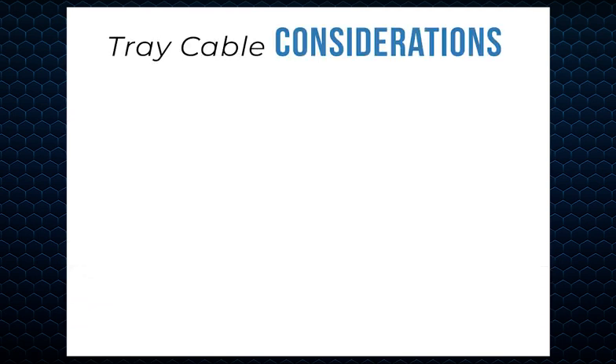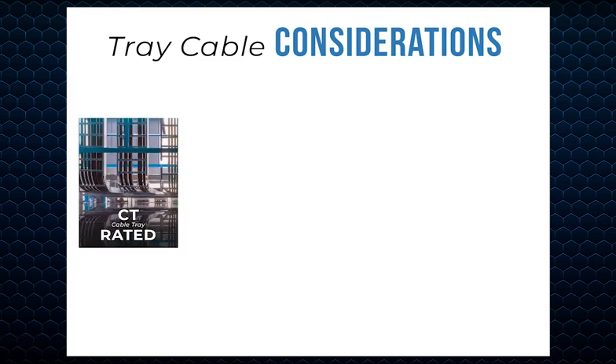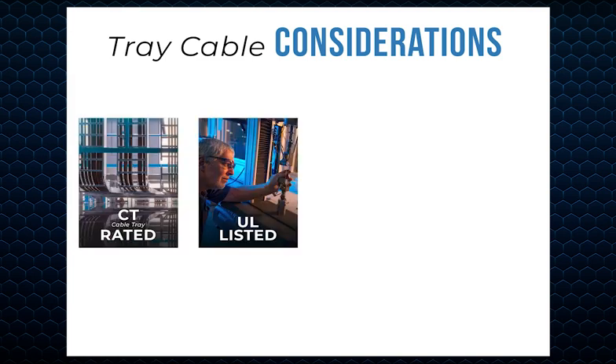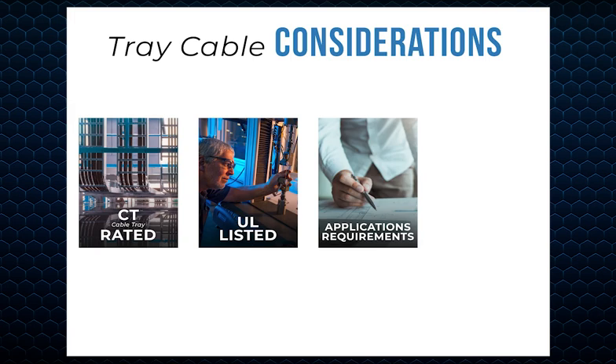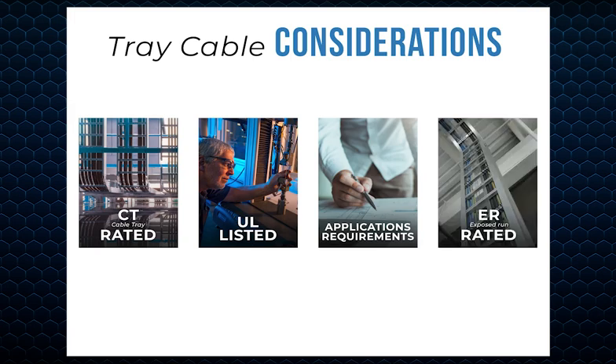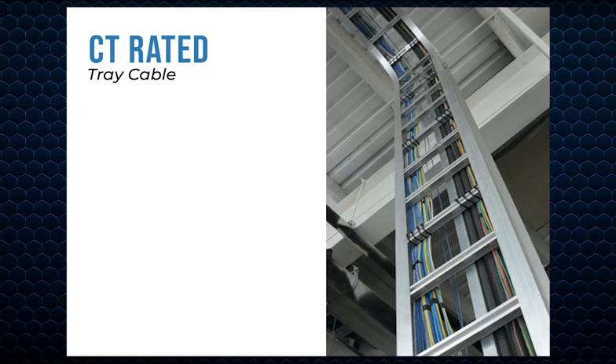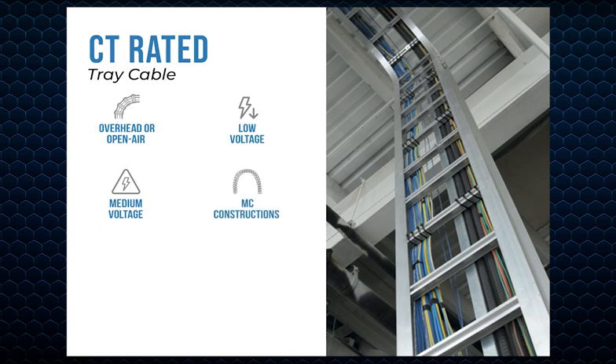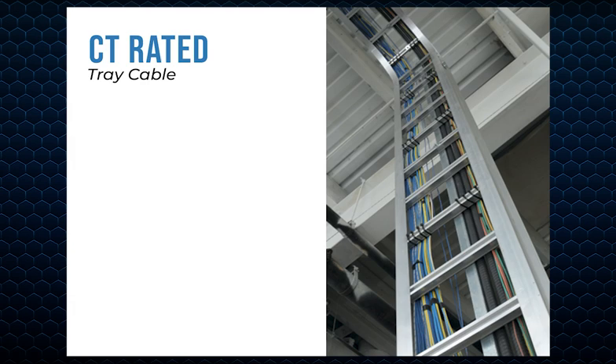There are 4 considerations when specifying tray cable. Is it CT rated? Does it have UL dual listing? What are the requirements of the application? And is it exposed run rated? CT rated refers to cable tray rated cables. Cables with this designation are suitable for use in overhead or open air cable tray and vertical trays. Single conductors for low voltage power, medium voltage cables, and metal clad constructions can be CT rated in certain size cables. CT rated tray cable refers to power and control cable that is listed as CT rated.